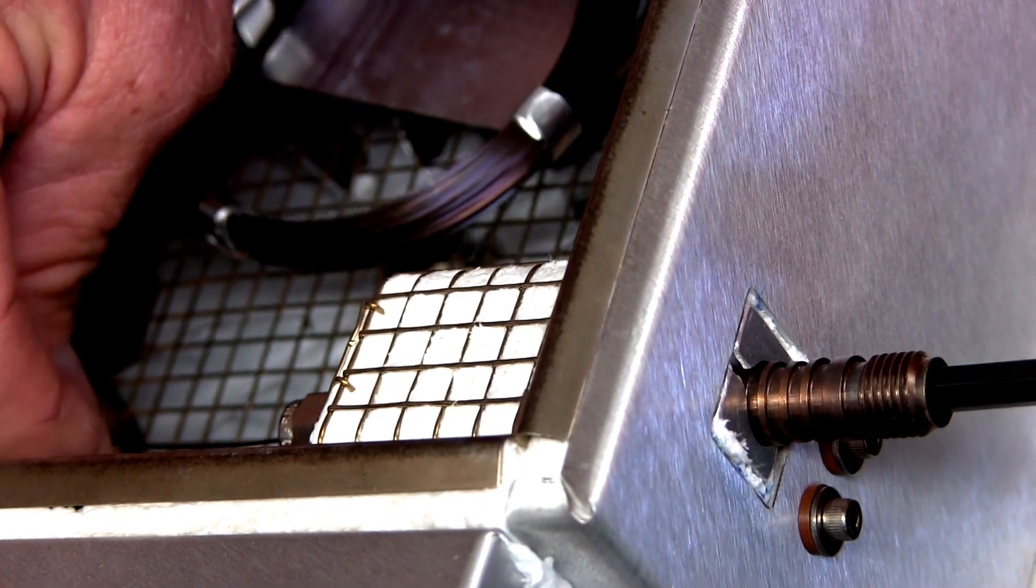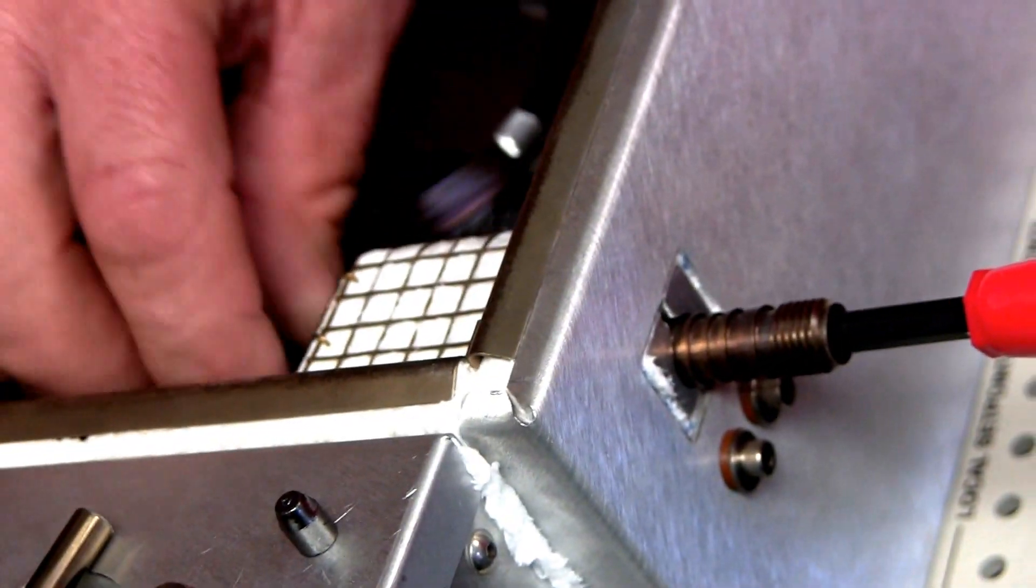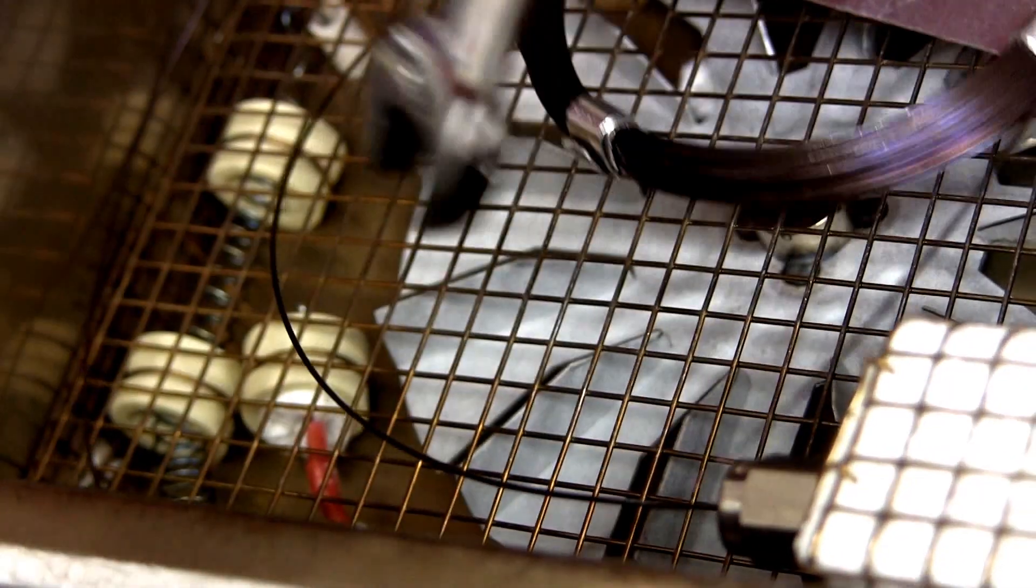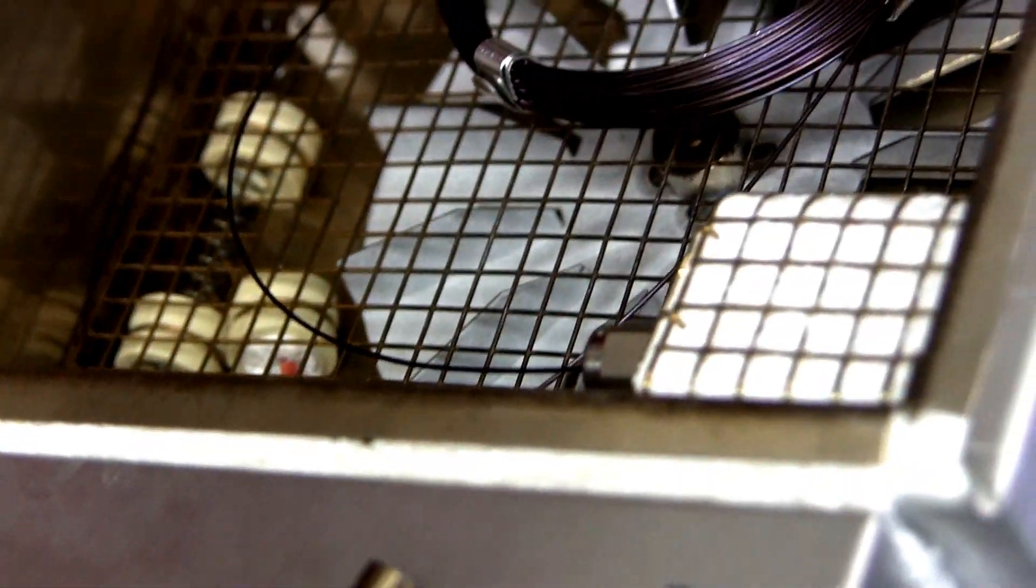I can feel it now. When I'm pushing this way, the column goes that way. When I push this way, the tool goes out. So wherever that tool bottoms out, that's the correct position for the column. And then you tighten it up. Now the nut should be tight enough that the column can't move even if you pull it as hard as you can. It should be really tight but not so tight that you damage this soft graphite ferrule.